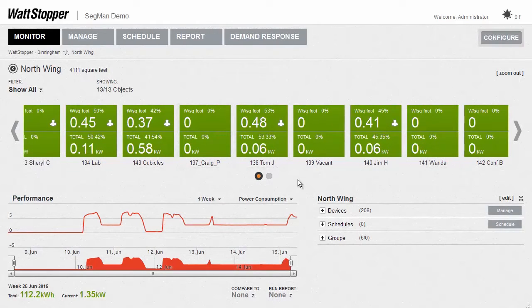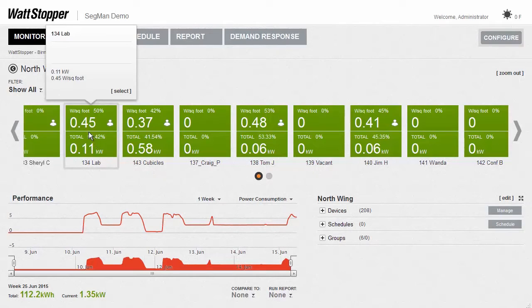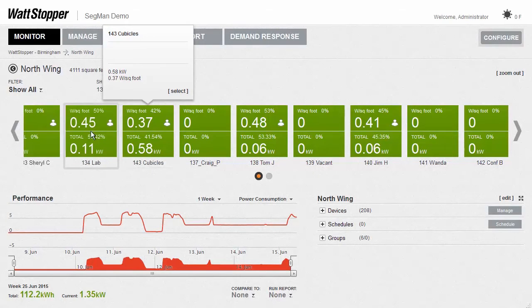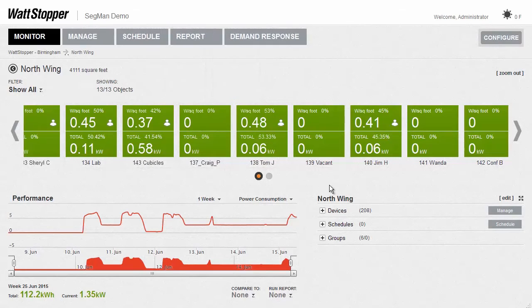Here is something really interesting. Notice the wattage of this room is less than the wattage of this room — so it must be more efficient, right? But that is not a fair comparison, because one room might be a lot larger than the other. What we've done is make it possible to enter the square footage of each room in LMCS or the Segment Manager's config screen, allowing us to normalize each room's usage by dividing its power by its square footage — giving you the lighting power density. All the energy codes are based on lighting power densities, but most owners have never seen the actual lighting power density for a space. Here it is displayed for every room.